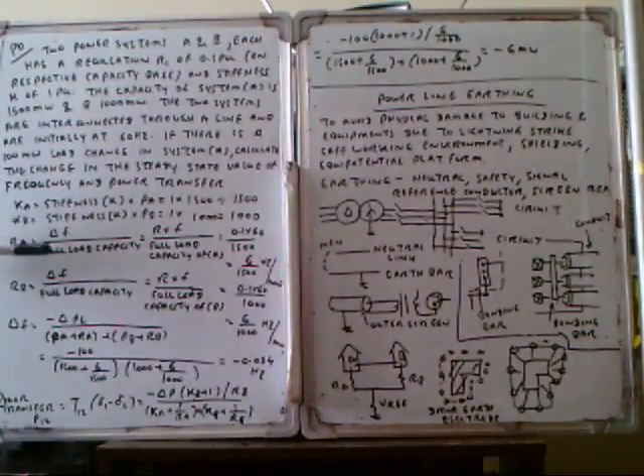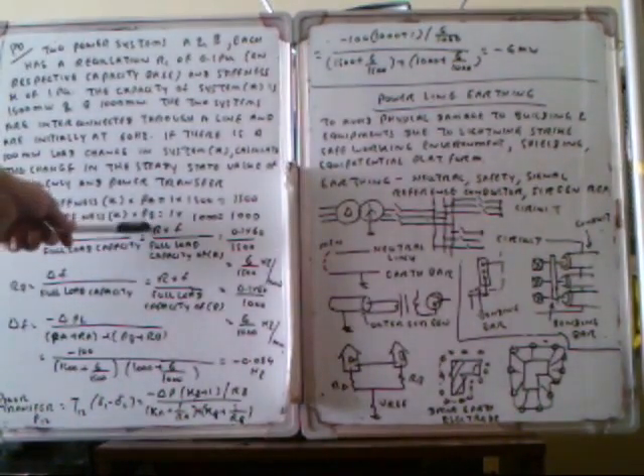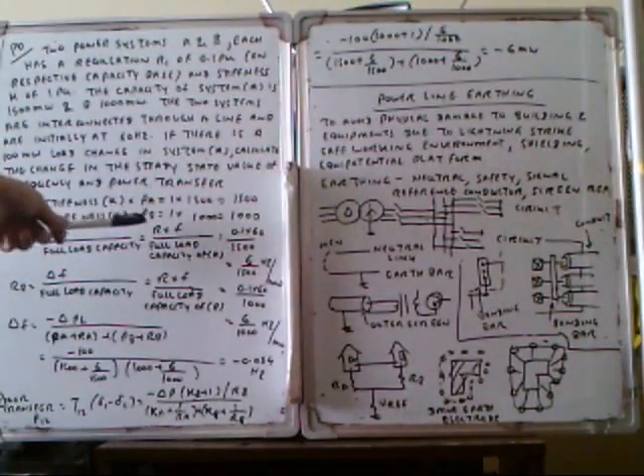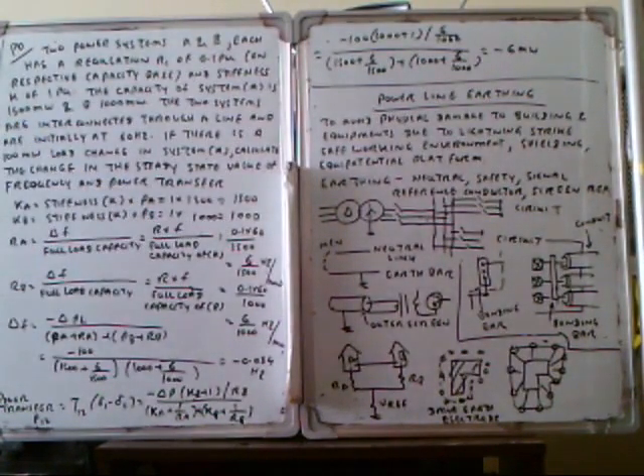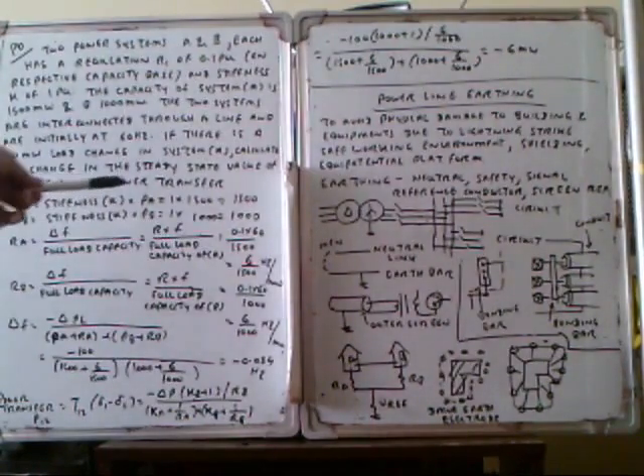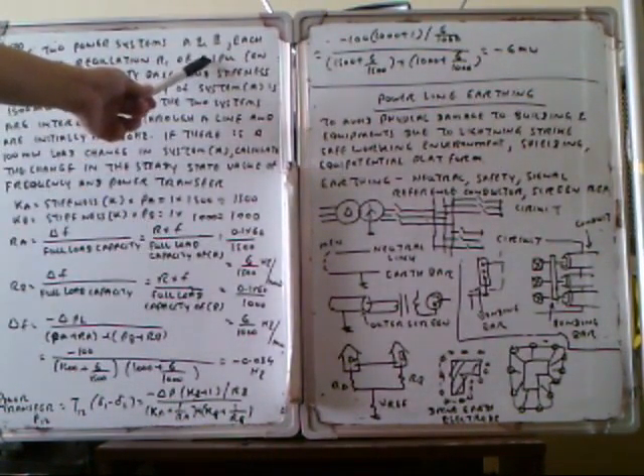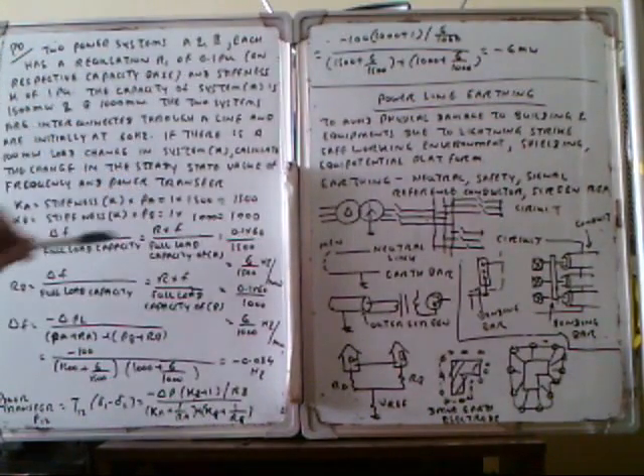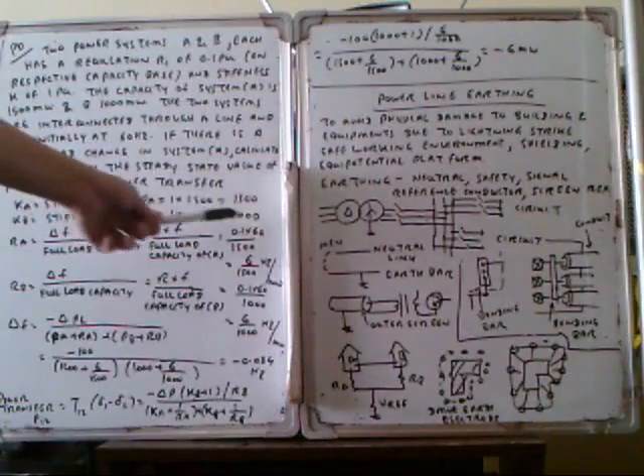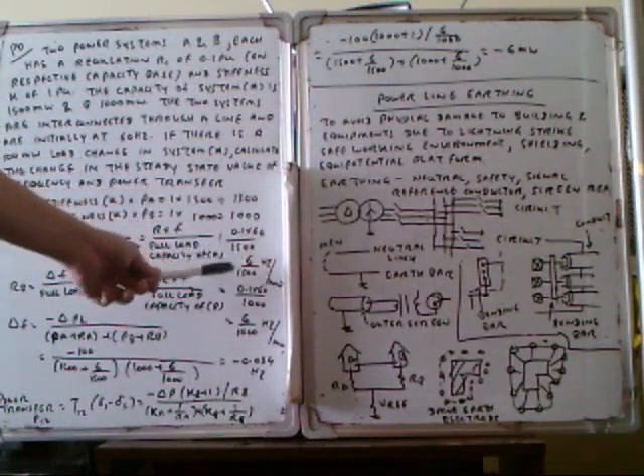R_A is delta F divided by full load capacity. So R multiplied by F divided by full load capacity of A. The regulation R is 0.1, frequency is 60 Hz, and full load capacity of A is 1500 MW, so you get 6 divided by 1500.